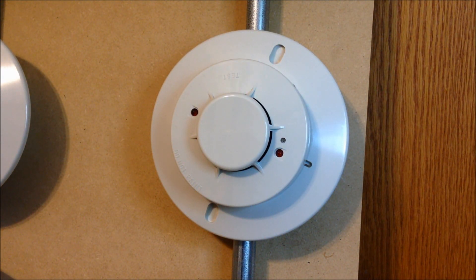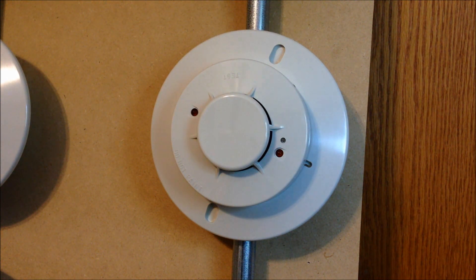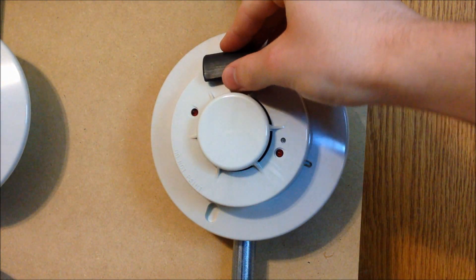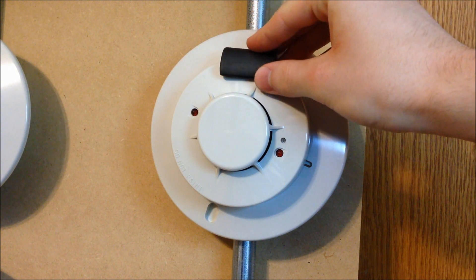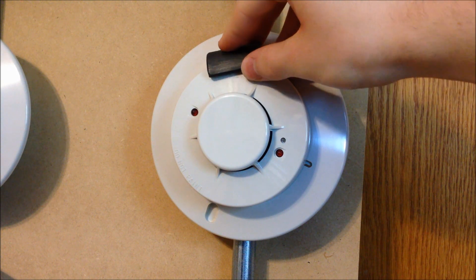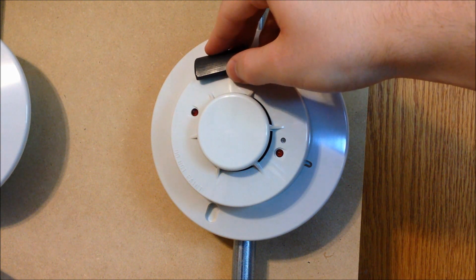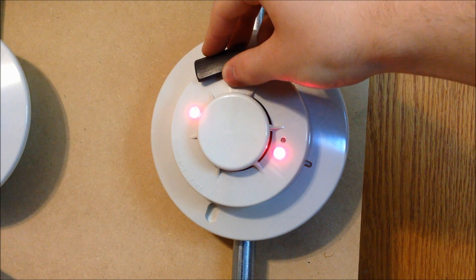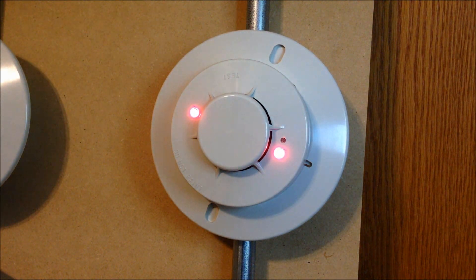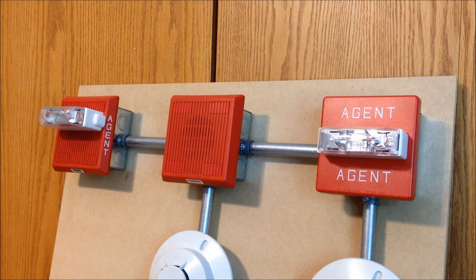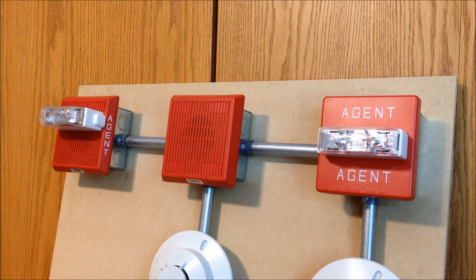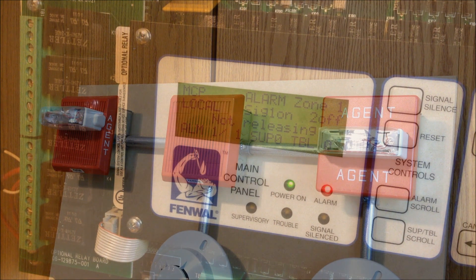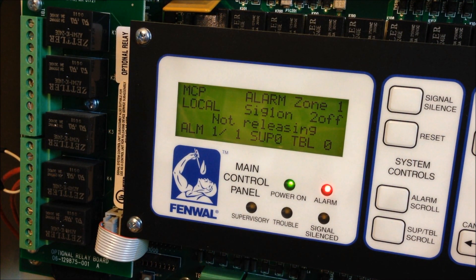I'm going to activate the PSD-7155 first, as it tends to be the easiest to activate with the magnetic test button. Once it goes into alarm, this will put the panel into the general alarm phase. You can see there are no strobes active and the middle horn is sounding Fenwal code 3. The message says 'not releasing' — it's only in general alarm — so the abort switch will not do anything until we activate another device.